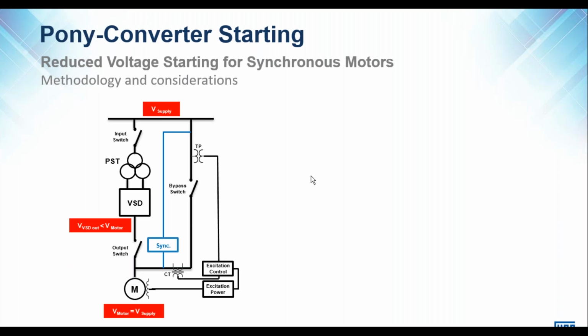Let me go through the next section. So essentially what we've discussed is a novel way of starting motors in circumstances where you want to apply a VSD to the start in order to get the benefits of starting the machine with a VSD, but where you are not using the VSD permanently connected to the machine. That, as I've already mentioned, is for applications where your end of curve load torque on your motor is less than the load torque applied after you get to acceleration.